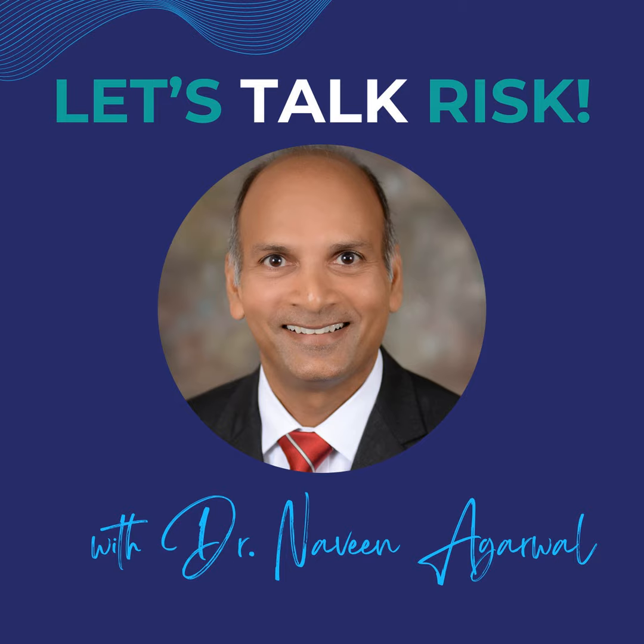Yeah, so the tasks are the things that are supposed to go right, and the risk analysis is really more concerned with the things that go wrong. But I would look at the task list, or the steps in the process, and highlight what those are, and when they can go wrong, what they relate to, and put that into the risk analysis.